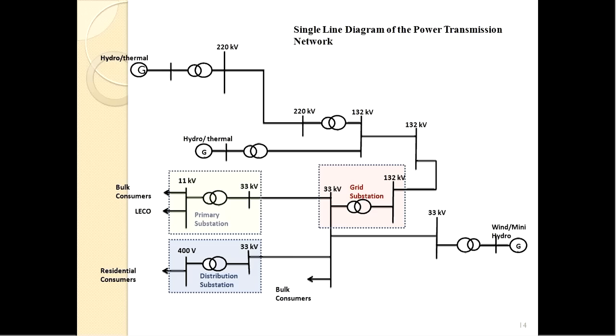This is basically your retail store near your home, and this is like the wholesale store. The energy is generated, transmitted, and here again converted to low voltage, and it may go as 33 kV and supply to bulk consumers on 11 kV, and to residents it will go as 33 kV, and using the 33 to 400 transformers near your houses, the distribution substations, the residential consumers will be served. So this is the conventional system.